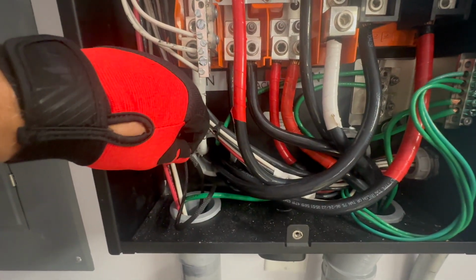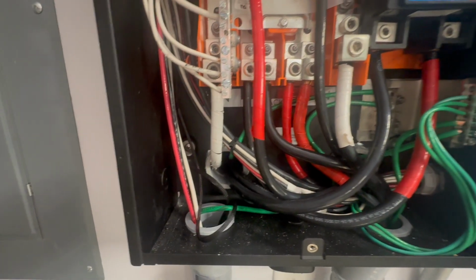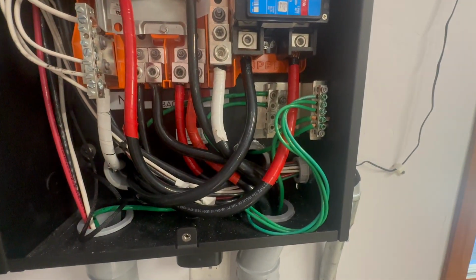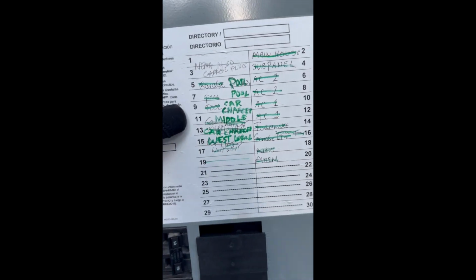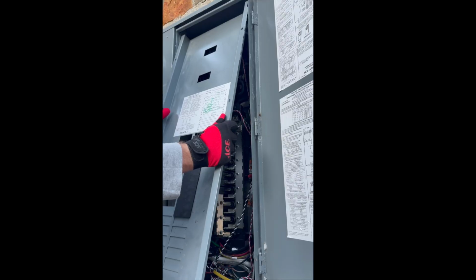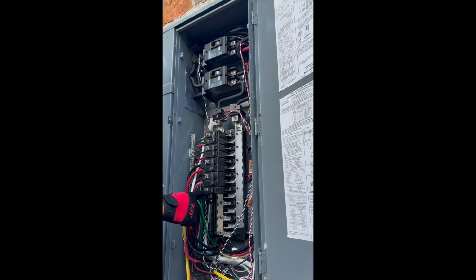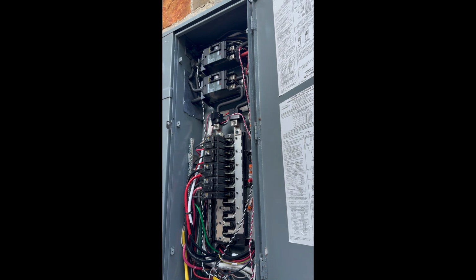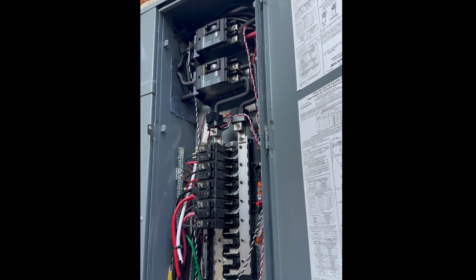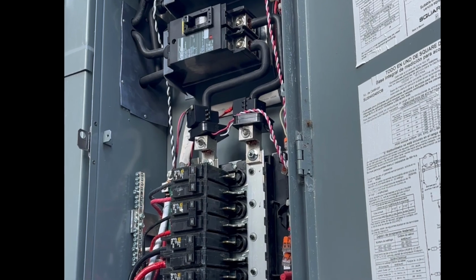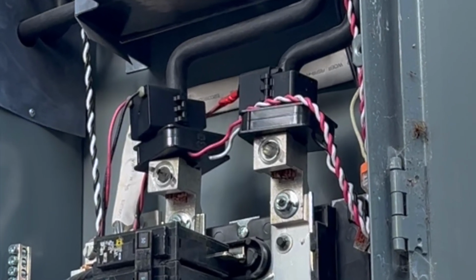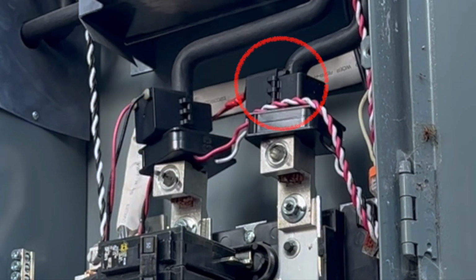I headed over to the panel that had the breaker for my EV charger to see if I could locate the other end of these CT wires. Alright, here is the label for the breaker for car charger west wall, and here's the breaker itself. Let's see if we can find the CTs. Alright, here's that EV charger breaker, and yeah, the two wires that feed this entire bank of breakers have a number of CTs on them. The two that look like the CT I found inside the backup gateway must be the Tesla CTs. And the other two are the ones from Sunpower for their metering system.